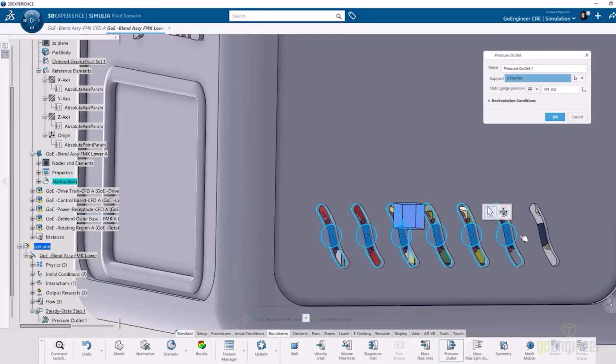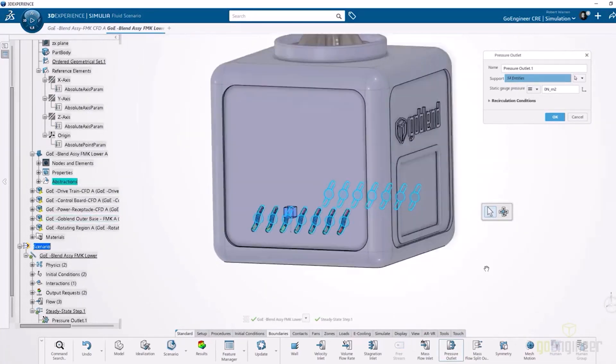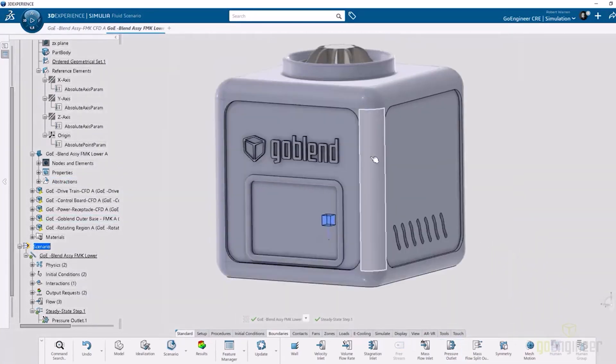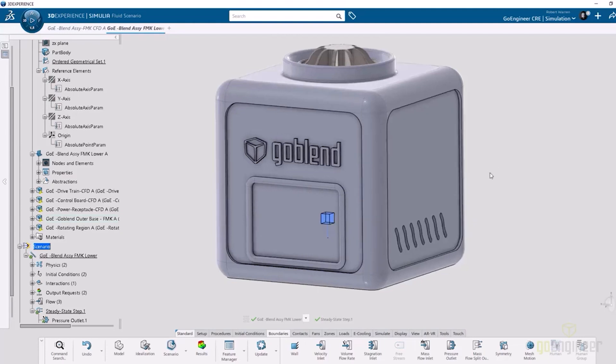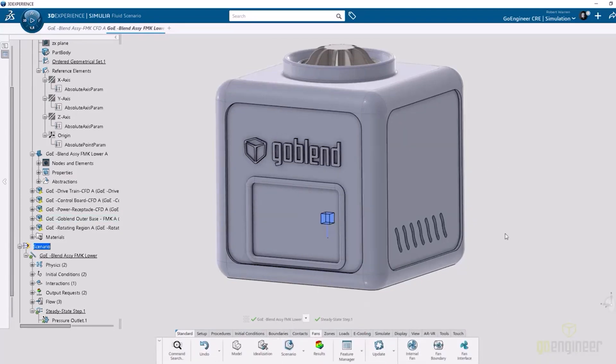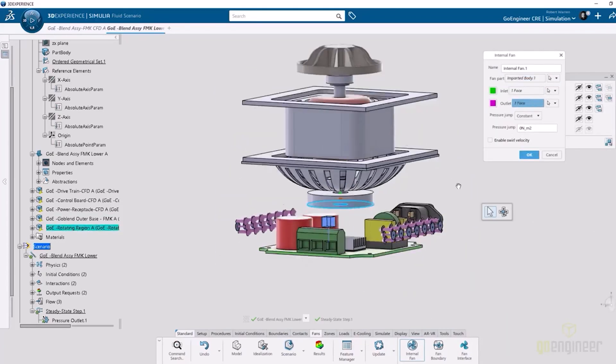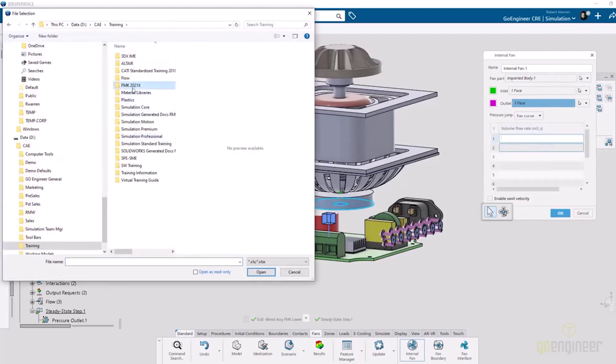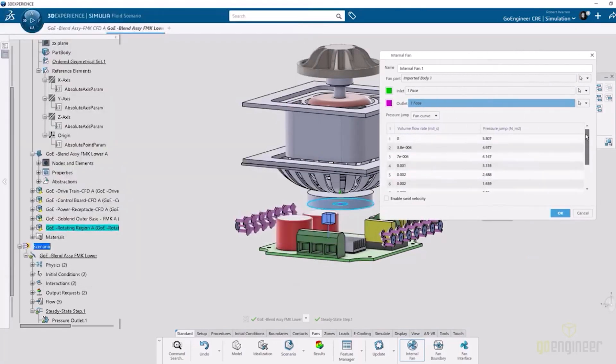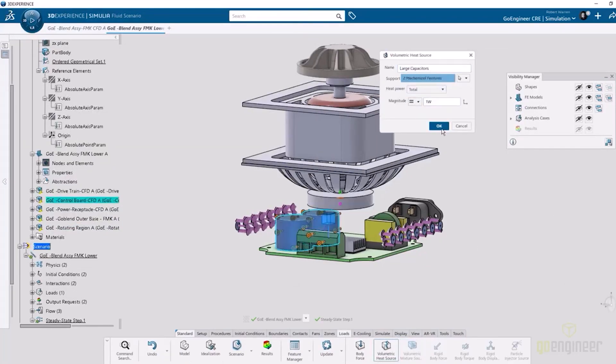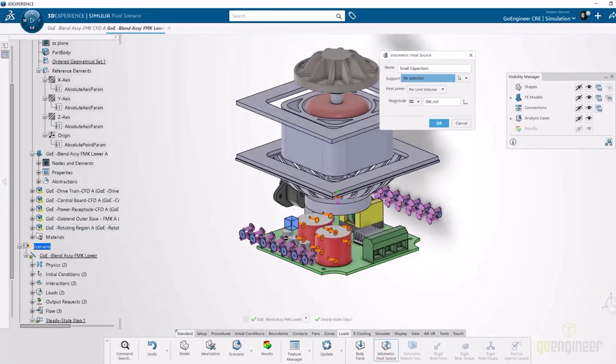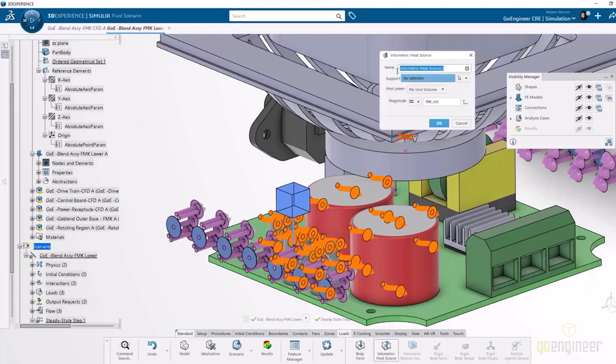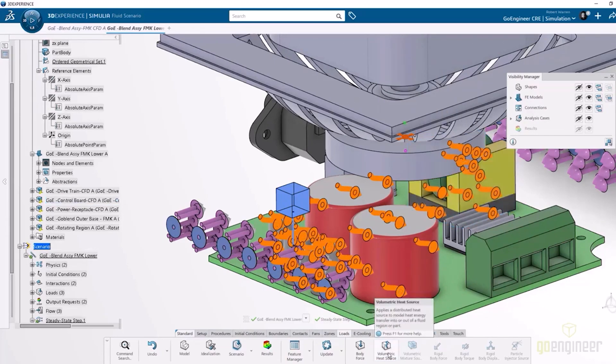From there we're going to set up the boundary conditions of the study. Here are my pressure outlets, specifying that that is ambient conditions. I'm going to add an internal fan, so I have a rough fan curve for what that blade would be producing at 1200 RPM. I'm going to specify my inlet and outlet face for that. I'm also adding my volumetric heat sources. I'm going to add a certain amount of heat power for the large capacitors, the small capacitors, the chip, the transformer, and all the other electrical components in the model.